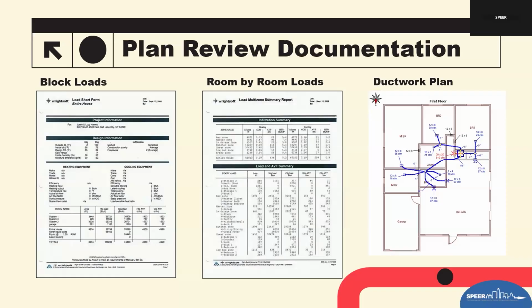I know a lot of cities just request the inclusion of Manual J, but they don't ask for S or D, and I'm assuming a lot of times the J is just a block load for the entire house. Technically, when we're verifying Manual D, you're going to need to see a room-by-room load to verify that the Manual D is meeting the room-by-room requirement from J, to make sure airflow is getting to where it needs to go.